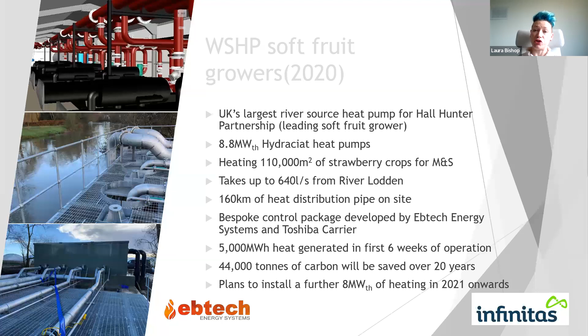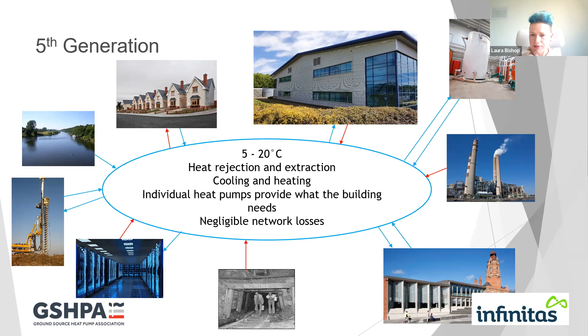So 5th generation, we've talked about ambient loops. This is where you have a cold heat network, 5 to 20 degrees C. You can have heat coming in from different sources - it could be a borehole system, a river, mine water, or waste heat from data centres. The buildings then extract that heat and use that energy for whatever each building needs. One building might need cooling and reject heat back into the network. Another might need heat at low temperatures, using a low temperature standard heat pump. Other buildings might need high temperature heat pumps, but they could all use the same energy. You've got to balance the network, but heat pumps are absolutely great for this kind of system.